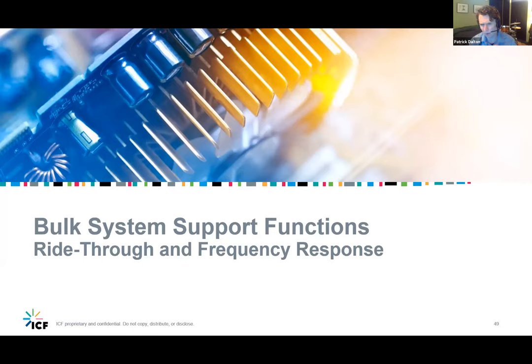And reactive power, it's not expended like active power is, it's exchanged. So consumption, absorption, injection might be a bit of a misnomer. I find them to be useful ways to talk about it. But reactive power is really being exchanged between systems and not necessarily consumed. So when we're talking about consuming, we're talking about a shift in the current waveform versus the voltage waveform, which is a little bit different than how we think about consuming active power, which is actually used to perform work, and that's less of an exchange, the exchange being more related to reactive, and active being more related to actual consumption.